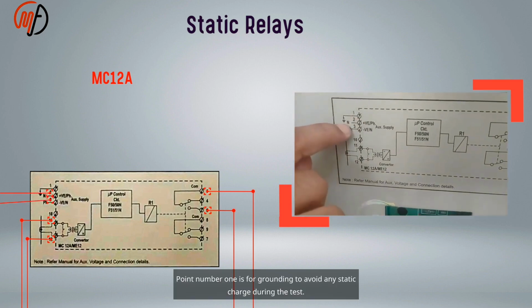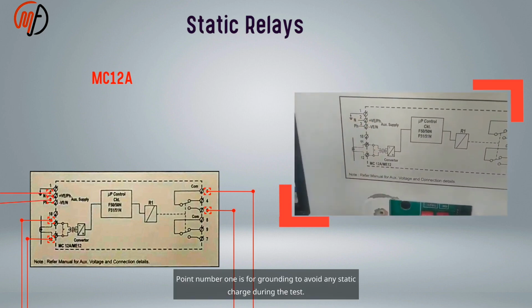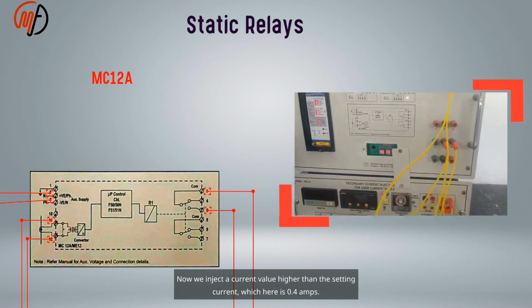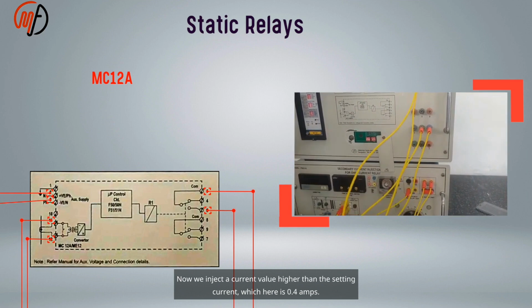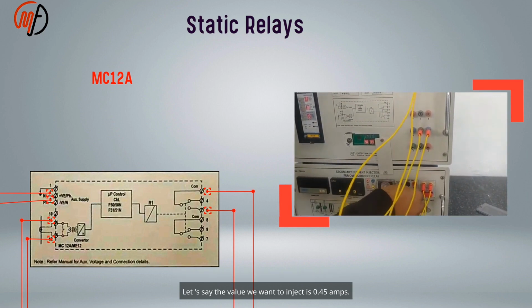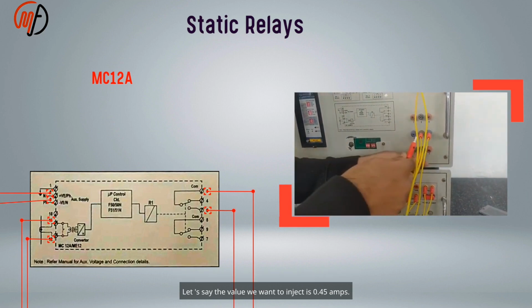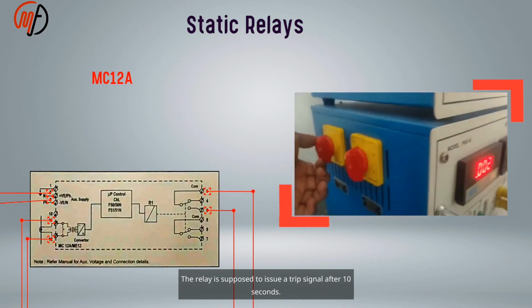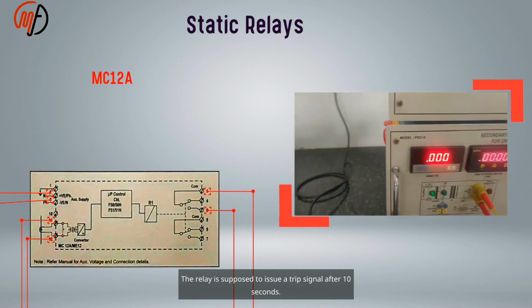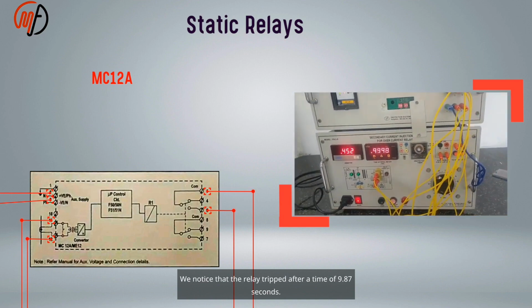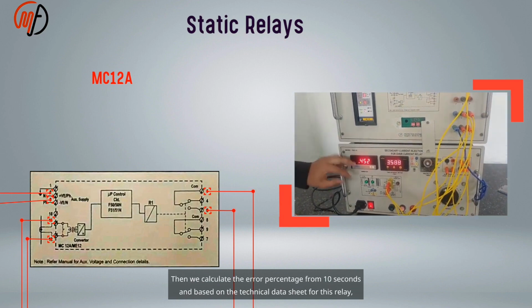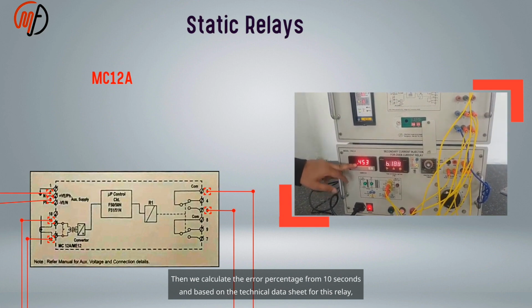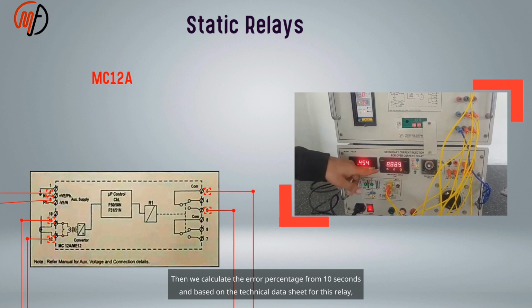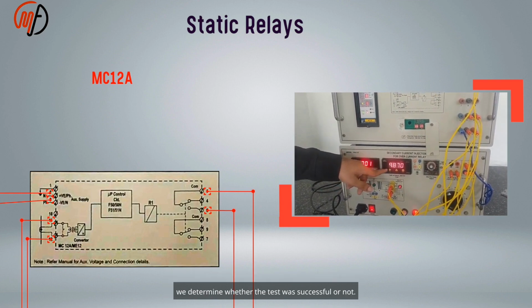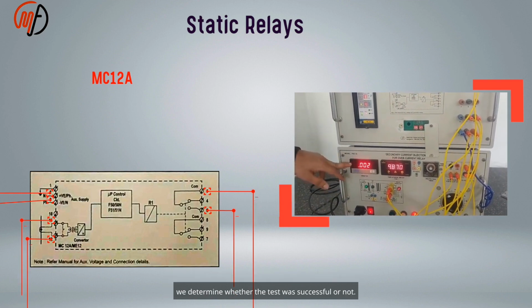Point number 1 is for grounding to avoid any static charge during the test. Now we inject a current value higher than the setting current, which here is 0.4 amps. Let's say the value we want to inject is 0.45 amps. The relay is supposed to issue a trip signal after 10 seconds. We notice that the relay tripped after a time of 9.87 seconds. Then we calculate the error percentage from 10 seconds, and based on the technical data sheet for this relay, we determine whether the test was successful or not.